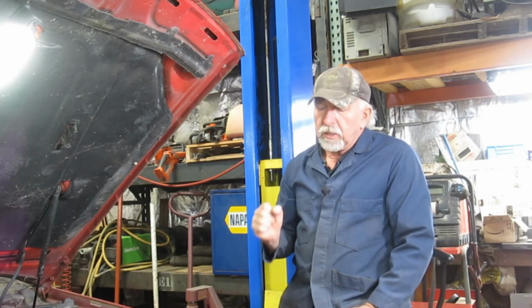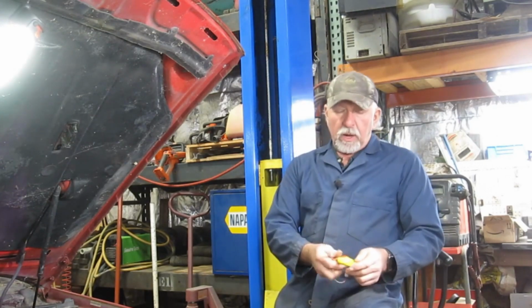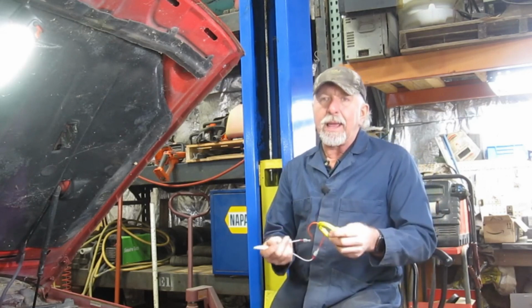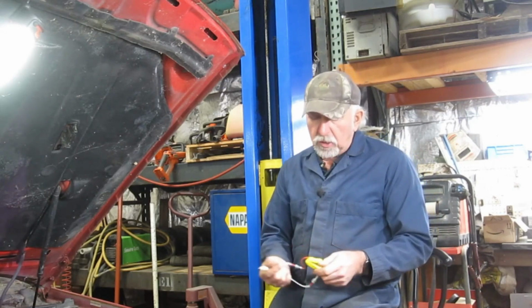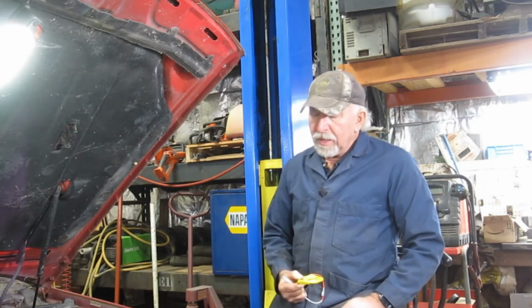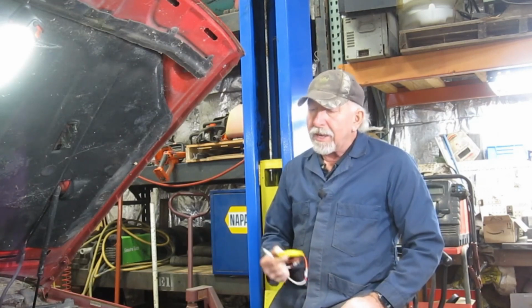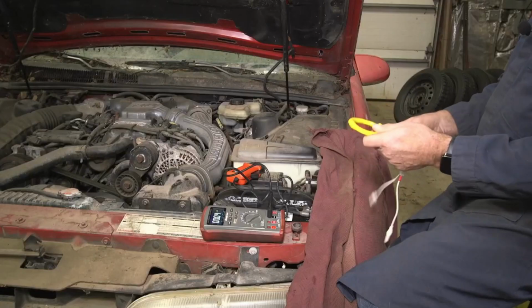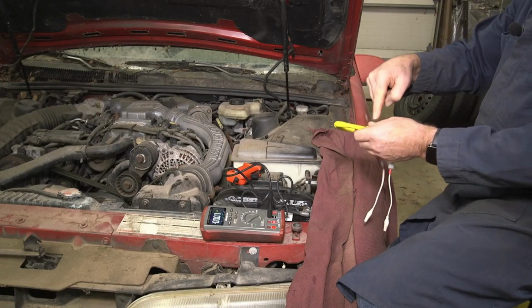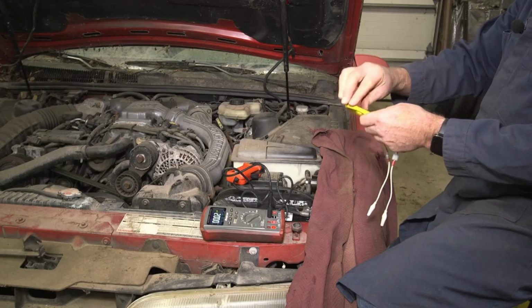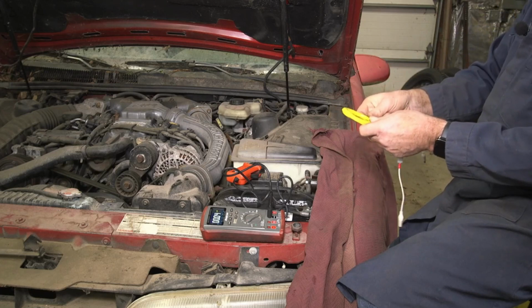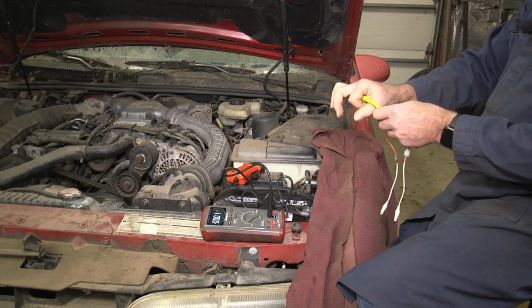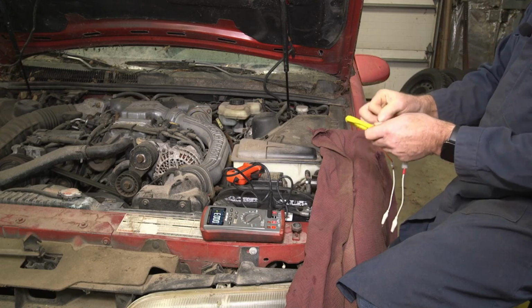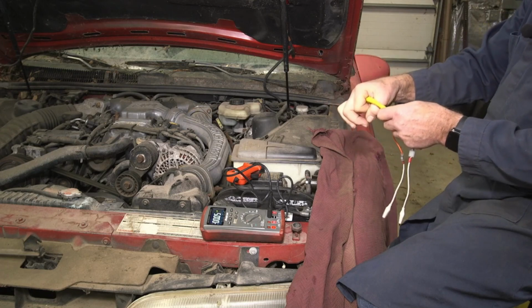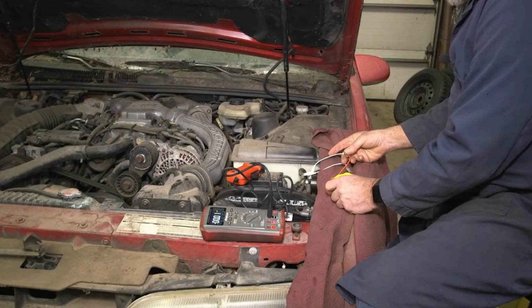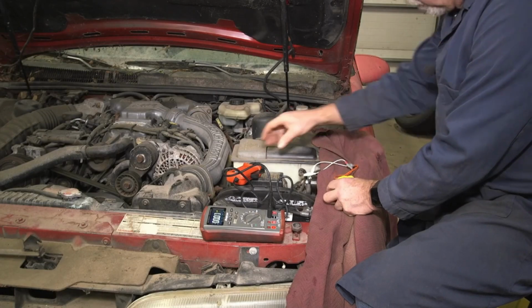What I'm going to do is one additional test using a 10 amp turn. This will magnify the signal coming in on the amp probe by 10 times — think of it as 10 cycles, or 10 strands of wire in a circle, which will magnetically increase the field by 10 times. We know this one here is going to be our power coming in.